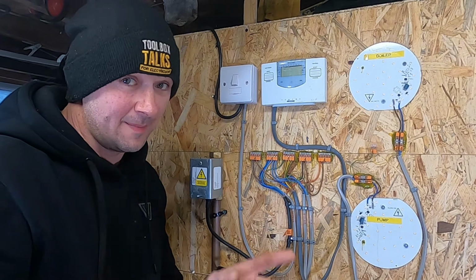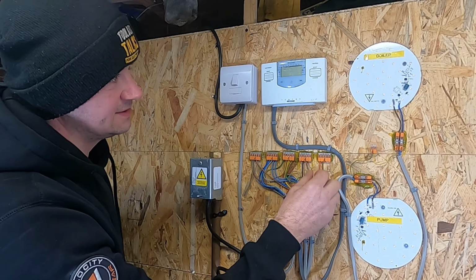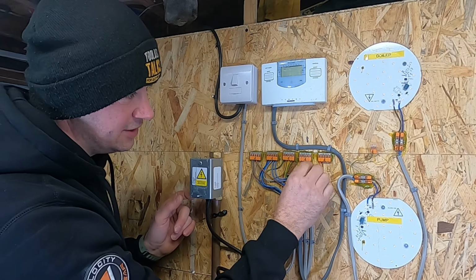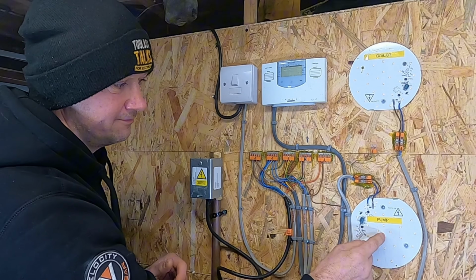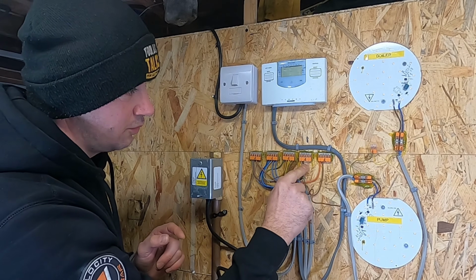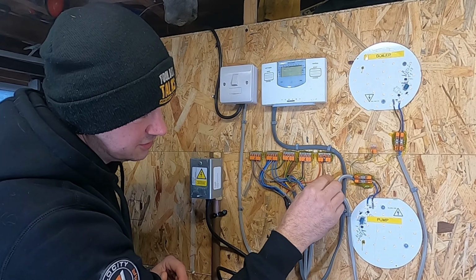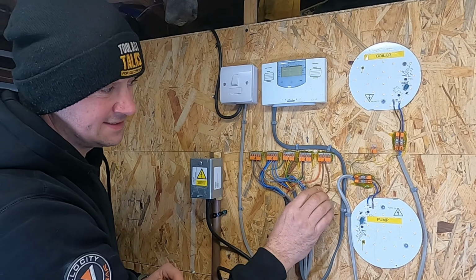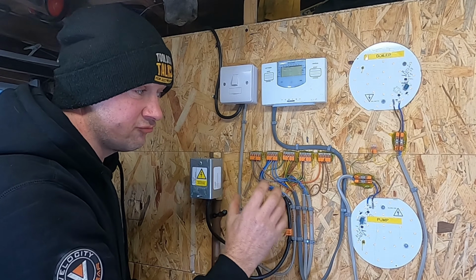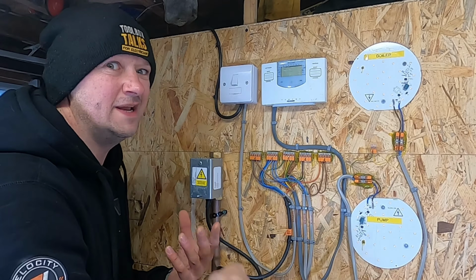So that was wrong for a couple of reasons. The pump supply, which I've got through here: when you turn the time clock on, it signals for the 2-port valve to open. It shouldn't signal the pump to come on, because you don't want the pump to come on until the 2-port valve is open. So where it should be is in with the orange, which is a signal to the boiler to come on and the pump to start to run. Because if the pump starts to run before the 2-port valve is open, it's just going to build up pressure within your heating system.